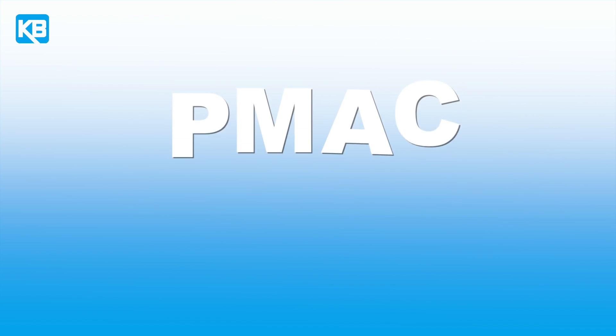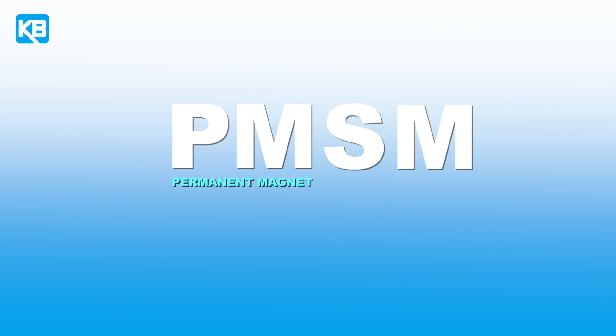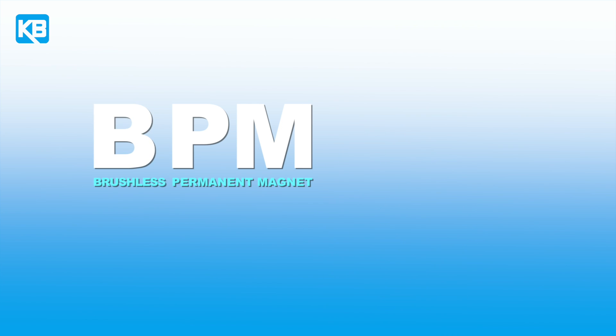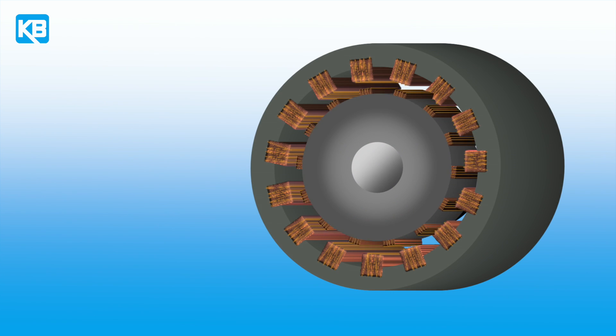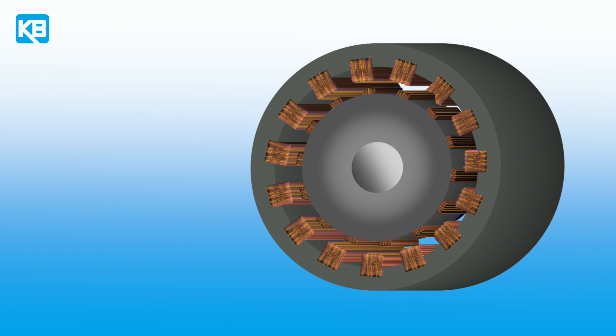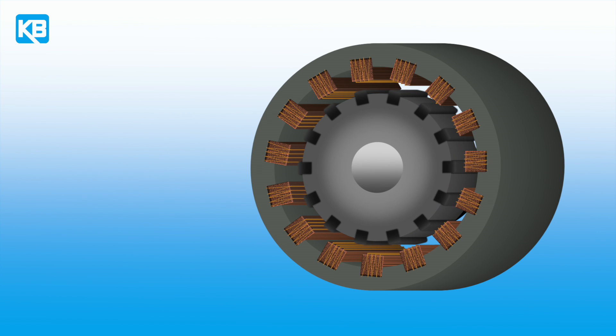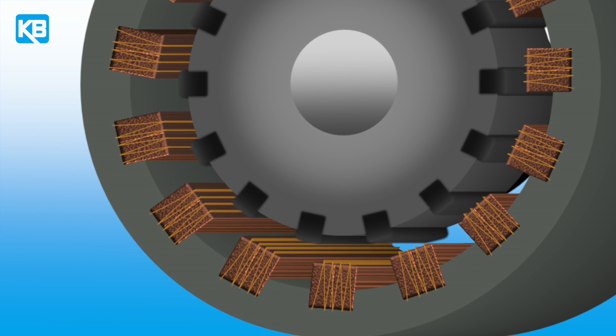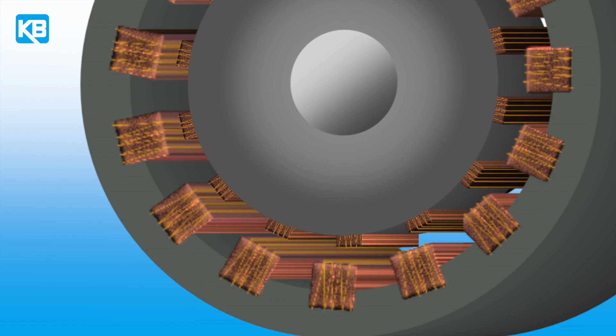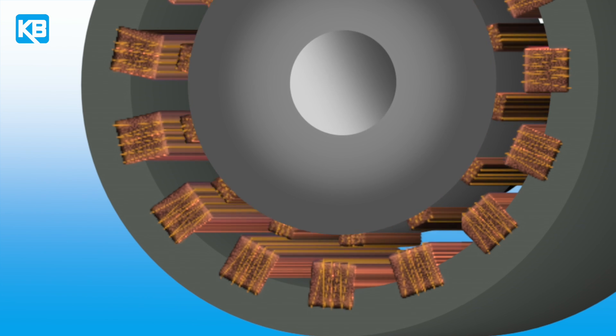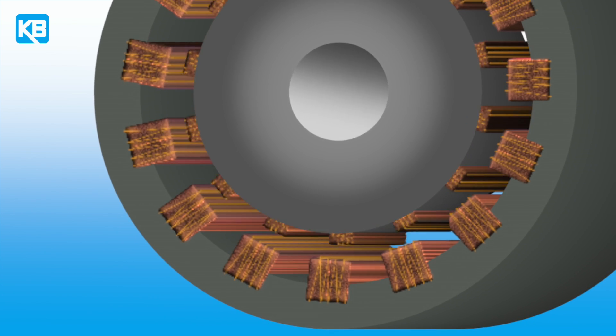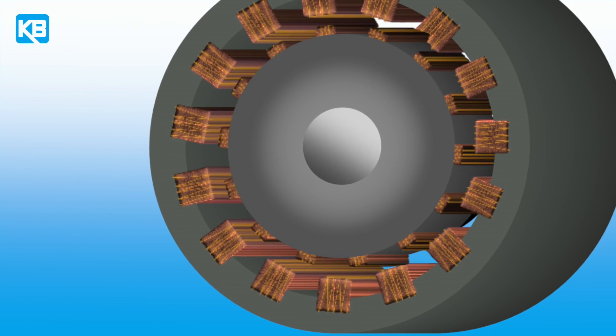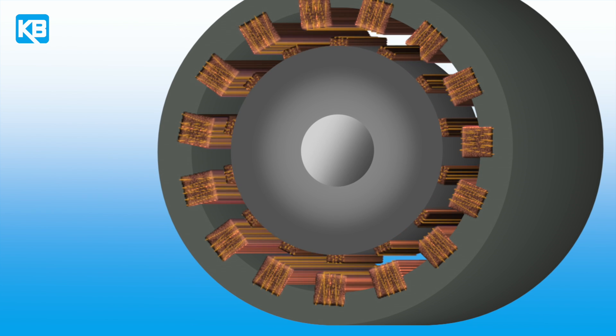PMAC, Permanent Magnet AC, PMSM, Permanent Magnet Synchronous Motor, BPM, Brushless Permanent Magnet. The very basic difference between AC induction motors and PMAC motors is the PMAC motor has magnet material on or in the rotor versus AC induction motors require current being induced into the rotor from the stator through the air gap and conducted through aluminum or other types of material bars in the slot of the rotor laminations.